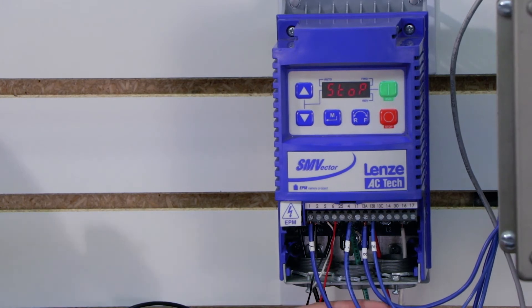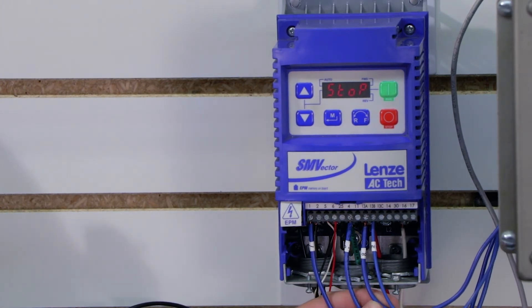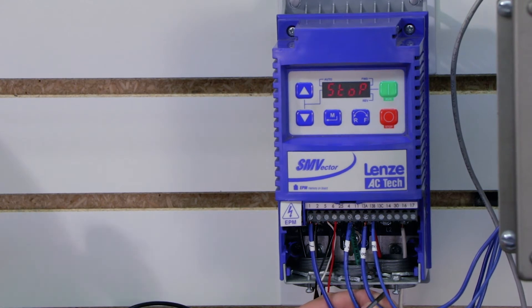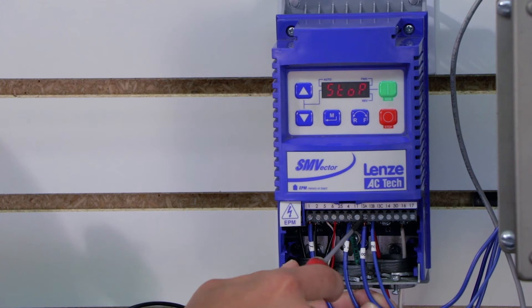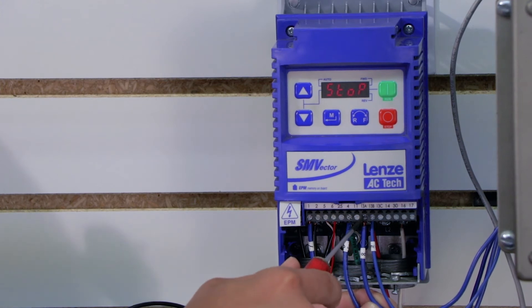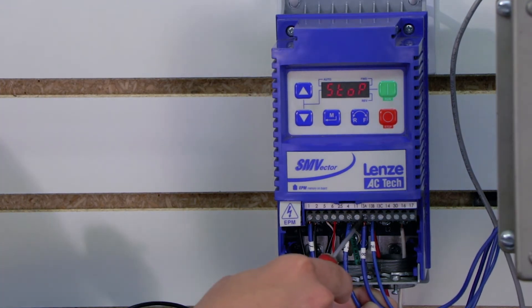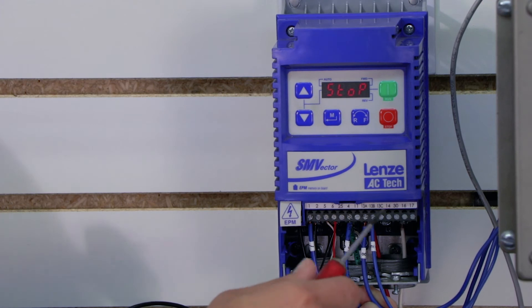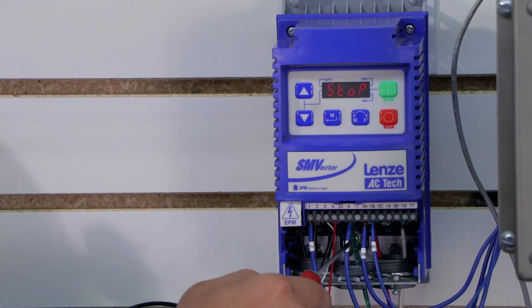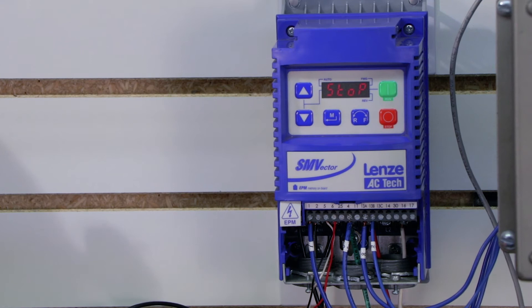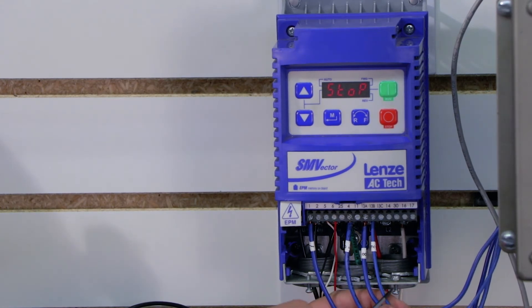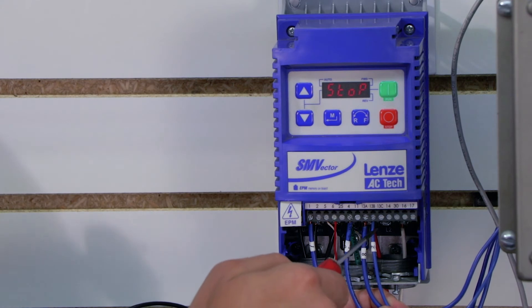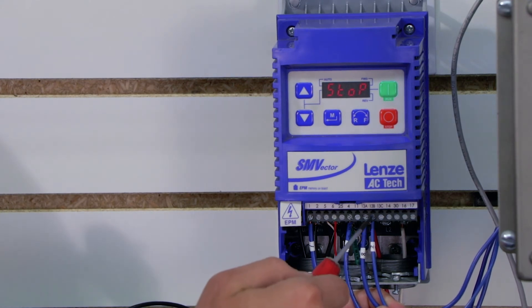4 then goes out to the side of our forward button, the normally open side of our forward button, and then it comes back on the other side of that normally open button to 13a. 13a, we're going to program for start forward. I'll do that here momentarily. 4 also goes to the front side of our reverse button on the normally open contact, and then it comes back from the other side of that normally open reverse button to 13b, which we will program for start reverse.